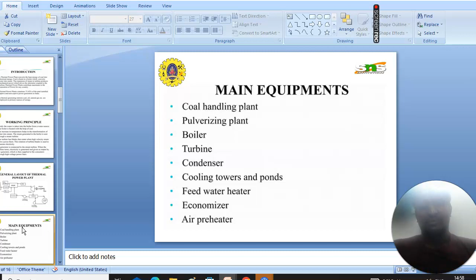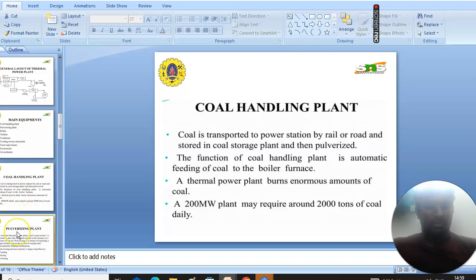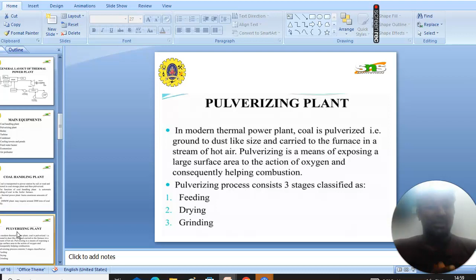The first is coal handling plant. The coal is transported to the power station with the help of rail or road. Thermal power plant burns enormous amount of coal. Generally, a 200 megawatt power plant may require around 2000 tons of coal daily. In modern power plants, coal is pulverized. It is done to expose a large surface area to the action of oxygen and consequently help combustion. Pulverization can be done in three stages such as feeding, drying, grinding.